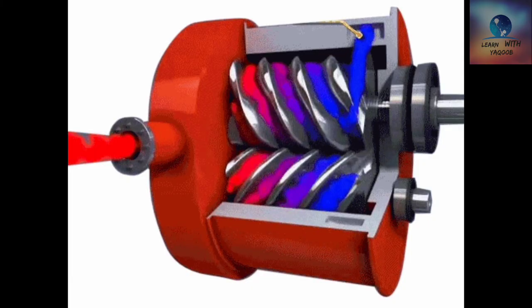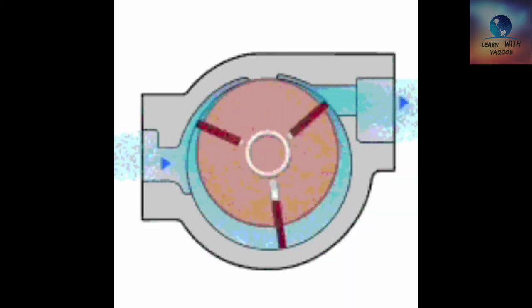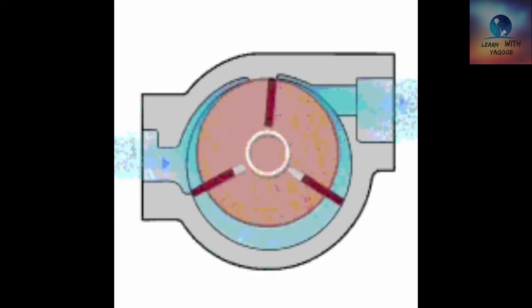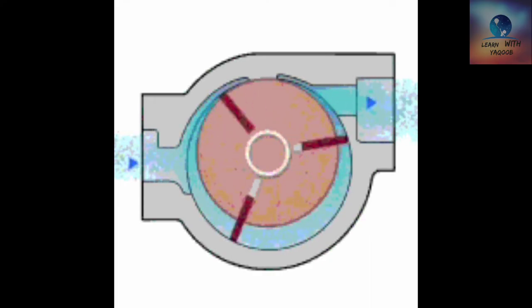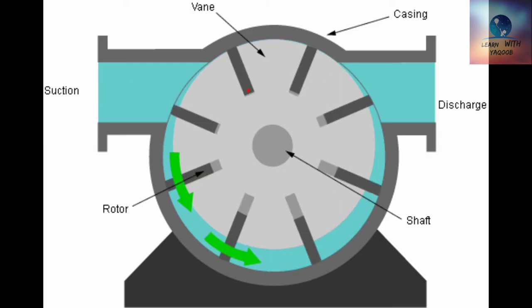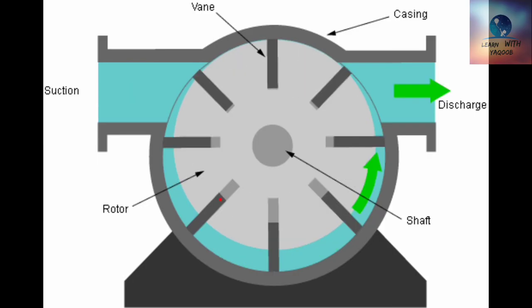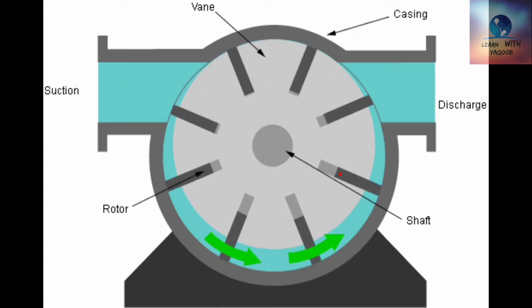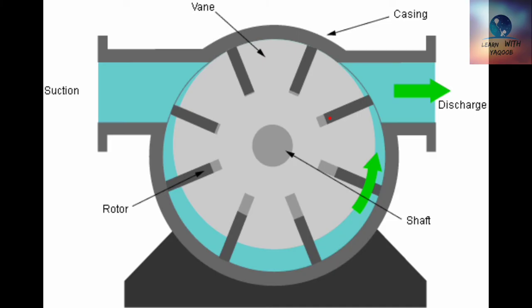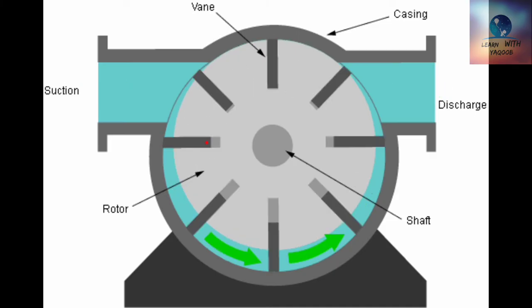A sliding vane compressor relies on a series of vanes mounted in a rotor which sweep along the inside wall of an eccentric cavity. The vanes, as they rotate from the suction side to the discharge side of the eccentric cavity, reduce the volume of space they are sweeping past, compressing the gas trapped within the space. The vanes glide along on an oil film which forms on the wall of the eccentric cavity, providing a seal.